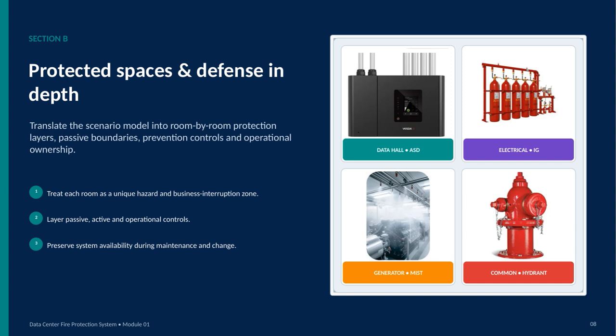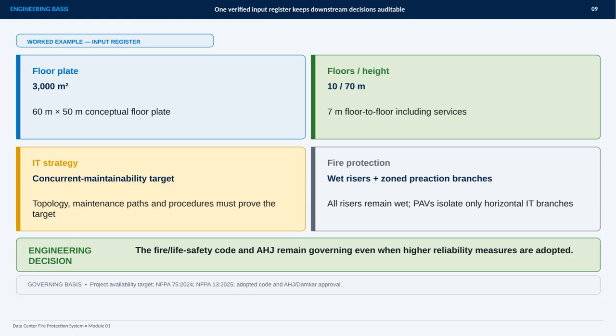This worked example shows how a verified input register creates an auditable engineering basis for downstream decisions. The key principle is that every major design choice should trace back to a defined, reviewable input. The conceptual floor plate is 3,000 square meters, based on a 60 by 50 meter layout. The project includes 10 floors, with an overall height of 70 meters, and a 7-meter floor-to-floor dimension that includes services.